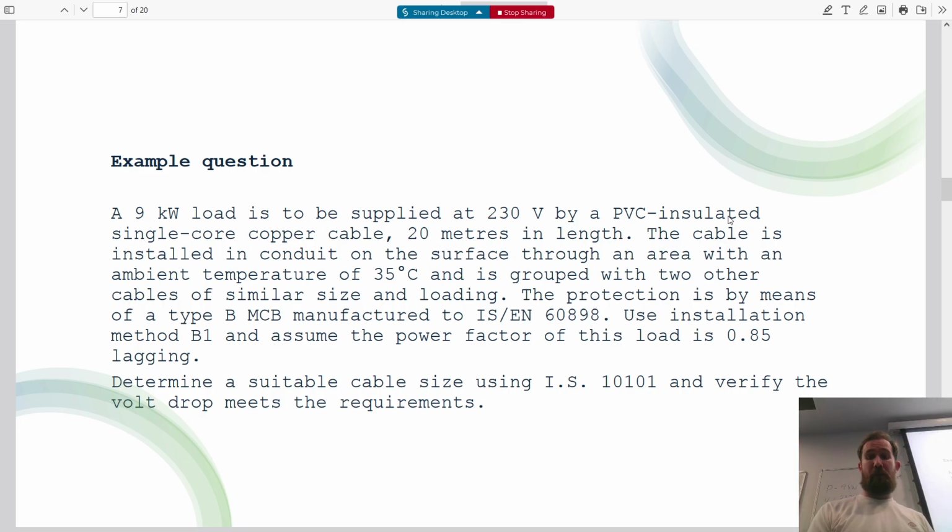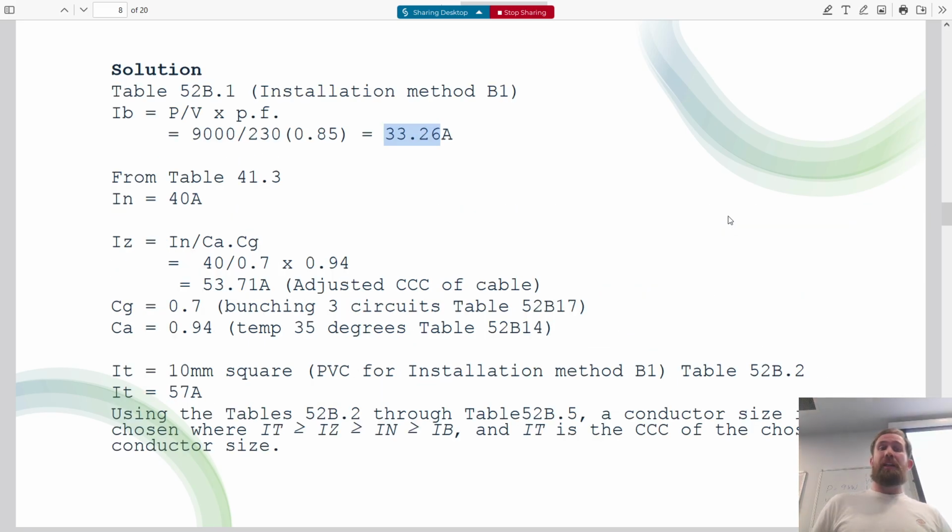And just for if you weren't in the class when we were doing this, the actual value of the conductor should be 16 squares. So if you are watching the video, you can see it on the board anyway. Wonderful. Let's reproduce this in Ecodial to see if we get the same results.